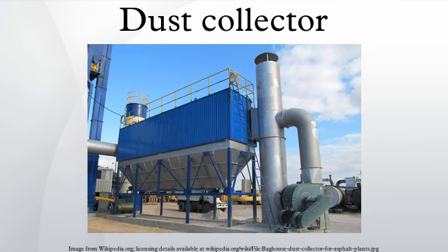Filter cleaning methods: online cleaning, automatically timed filter cleaning which allows for continuous, uninterrupted dust collector operation for heavy dust operations. Offline cleaning, filter cleaning accomplished during dust collector shutdown. Practical whenever the dust loading in each dust collector cycle does not exceed the filter capacity. Allows for maximum effectiveness in dislodging and disposing of dust.